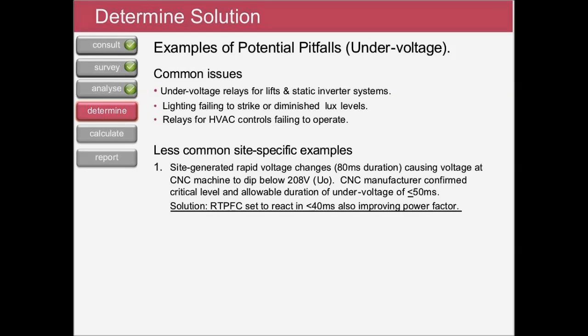An example from one of our recent industrial clients: we saw a site generate an infrequent voltage dip below 208 volts. This had a duration of around 80 milliseconds. Now, this was causing a number of CNC machines on site to drop out on low voltage. These machines had a maximum tolerance of 50 milliseconds before they failed, and this was confirmed by the CNC manufacturer. Now, by introducing real-time power factor correction, we could not only improve the power factor, dampening the inrush currents, but the specified solution was able to react in less than 40 milliseconds. Obviously, this increased the stability of the entire process.